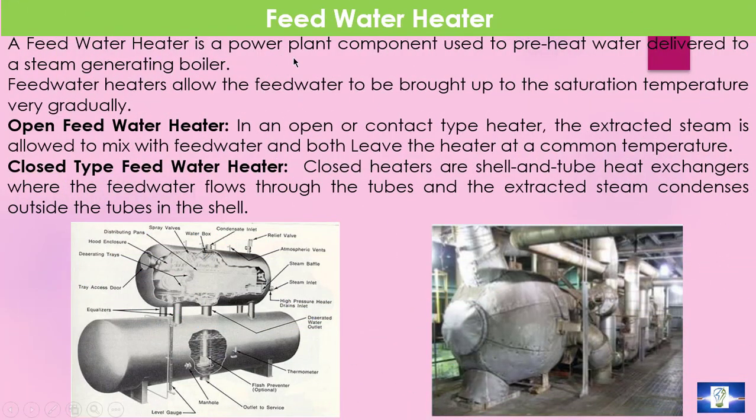A feed water heater is a power plant component used to preheat water delivered to a steam generating boiler. Preheating the feed water reduces the irreversibilities involved in steam generation and therefore improves the thermodynamic efficiency of the system. This reduces plant operating costs and also helps to avoid thermal shock to the boiler metal when the feed water is introduced back into the steam cycle.